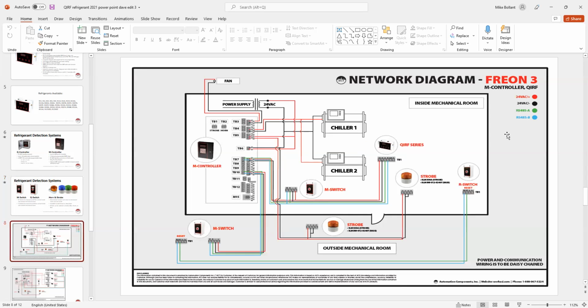So I think this network diagram right here kind of explains everything that's going on. Let's say you've got the two chillers there, and they're both the same Freon. You've got one QIRF in the middle there, which communicates back RS-485 to the M controller. We have an override switch in the room and outside the room, and also a strobe outside the room and inside the room. We also offer a remote switch for reset if you need to override.